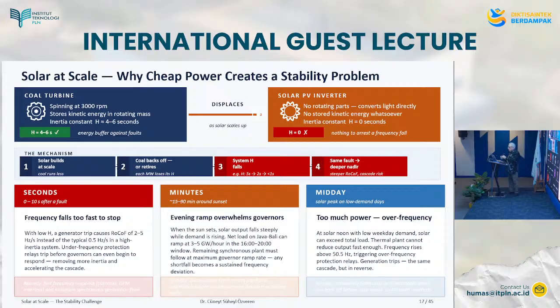So here the figure I have is that net load on Java Bali can ramp at 3 to 5 gigawatts per hour. Okay, 3 to 5 gigawatts per hour. So if you've got solar which is greater than 5 gigawatts, right, you need 1 hour advance. You need to know 1 hour in advance to start increasing the output of your generators, because 1 hour later you'll lose the solar input. Okay, so you need to start increasing your generators.